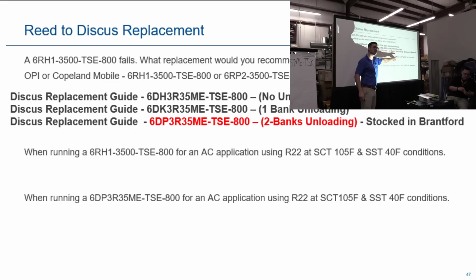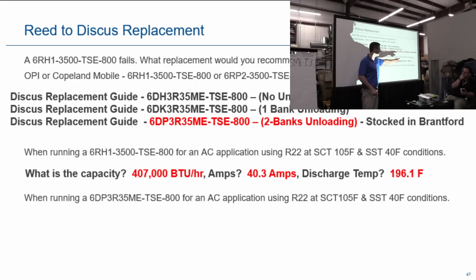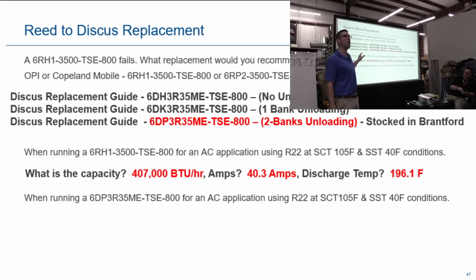R22 at those conditions, 105 and 40. This is it. The capacity is 407,000 BTUs, 40.3 amps, and discharge is 196. Everybody see that? You can go in the Copeland Mobile and do this if you want, but I'm just doing it pretty quick. Now we change this, replace it with the Discus I just talked about.